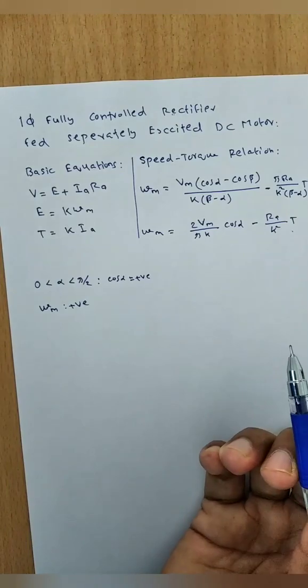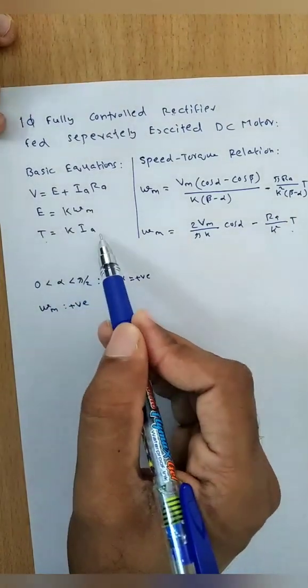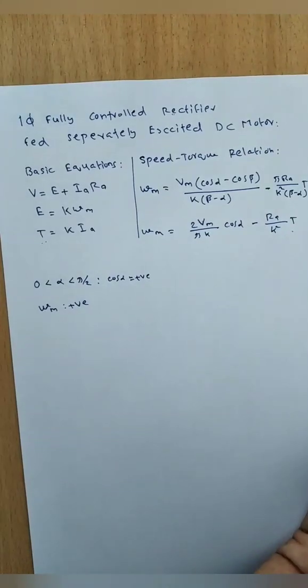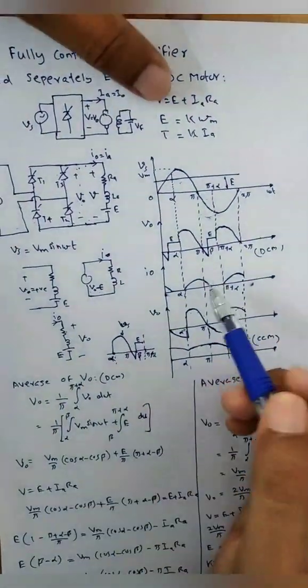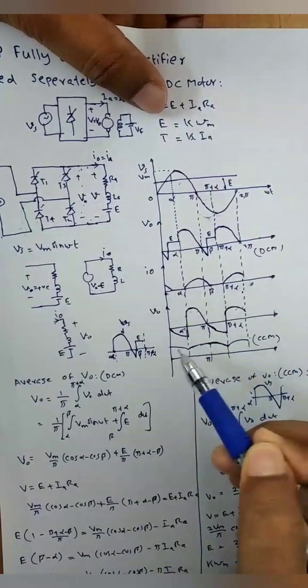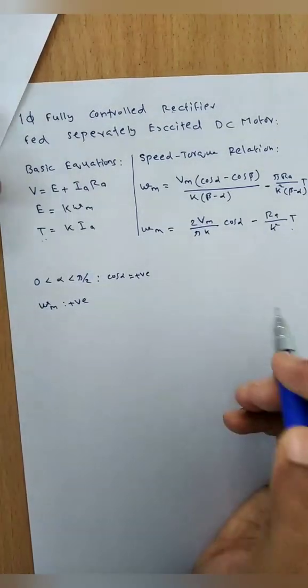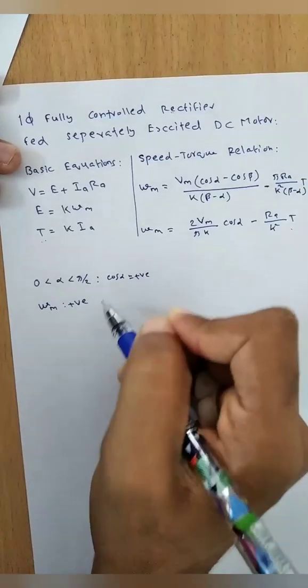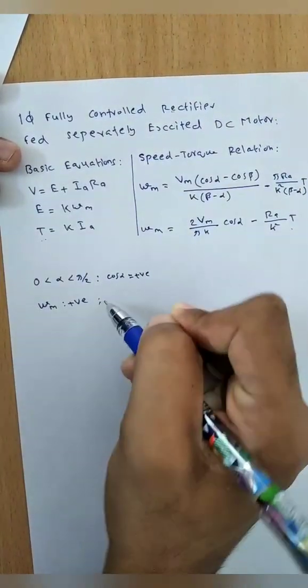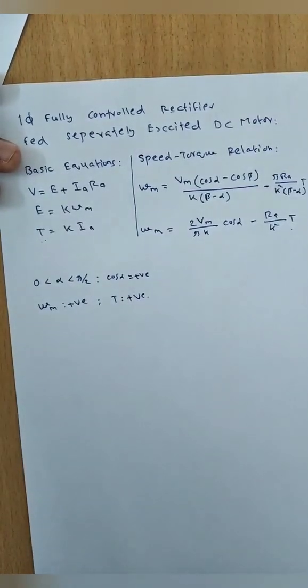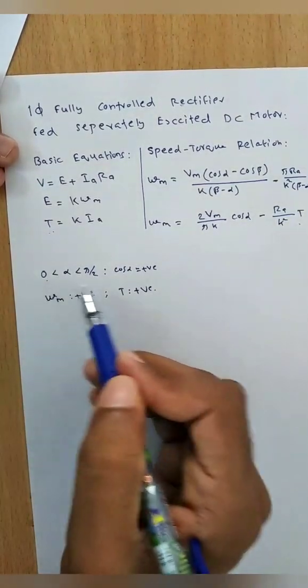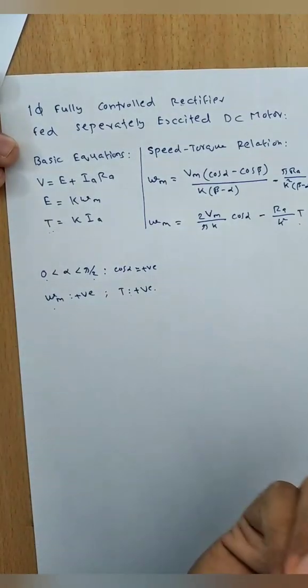Looking at torque: T = K × i_a, so the polarity of torque depends upon the polarity of i_a. In a controlled rectifier, both in continuous conduction mode and discontinuous conduction mode, i_0 is always positive. The average value i_a is always positive for any alpha. Since i_a is positive, torque is always positive.